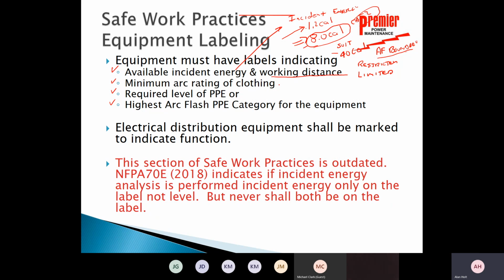Then it talks about the minimum arc rating of clothing. That's going to be this incident energy level. They may actually specifically write on their labels what arc flash clothing you've got to have. Required level of PPE or category. They may still use that category, which would be category 1, 2, 3, 4. But the latest edition of NFPA 70E states that if you've got the incident energy on the label, you cannot have the PPE category on it. So I would not expect them to. I mean, Marathon's good about following all the policies, and so they may not have changed or revised this policy to pick up on the latest standard yet. But you should not see the PPE category if you have the incident energy.